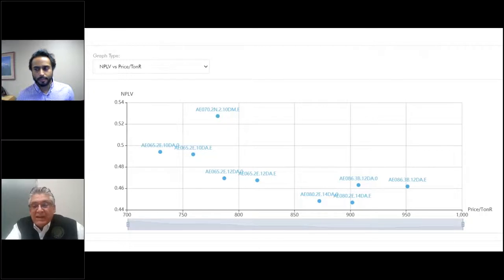I want to share with you, if I can, when we look at air-cooled or water-cooled machines, whenever we're doing a selection and looking for solutions to a design that you're working on, a lot of it comes down to efficiency versus cost per ton. Our job is to make sure we get you the highest efficiency for the lowest cost per ton. That's the main goal for you and your customer. In this case, this is a screenshot of an NPLV standard, and along the bottom is the price per ton, and the vertical axis is the actual kW per ton. I don't know if you can see my mouse on there? You can? Okay, good.